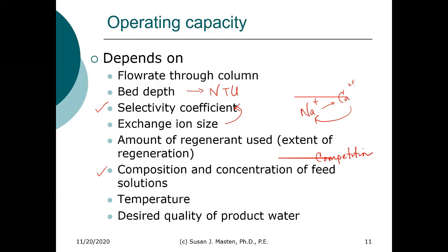Temperature also plays a role. If you increase temperature, the pressure drop across the resin decreases, and that's because the pressure drop is directly proportional to the viscosity of the liquid. And we know that viscosity decreases as temperature increases.